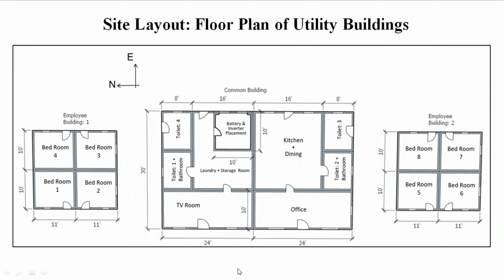Floor plan for utility buildings. A common building will have a TV room, an office, kitchen, dining area, laundry storage area, as well as toilets and bathrooms. Initially, we thought of having a separate electrical room behind this common building, but then found that the laundry storage area was large enough, so we have kept a 10 by 10 room for battery inverter placement, and this small room has 2 windows so that battery heat can be easily dissipated through natural ventilation.